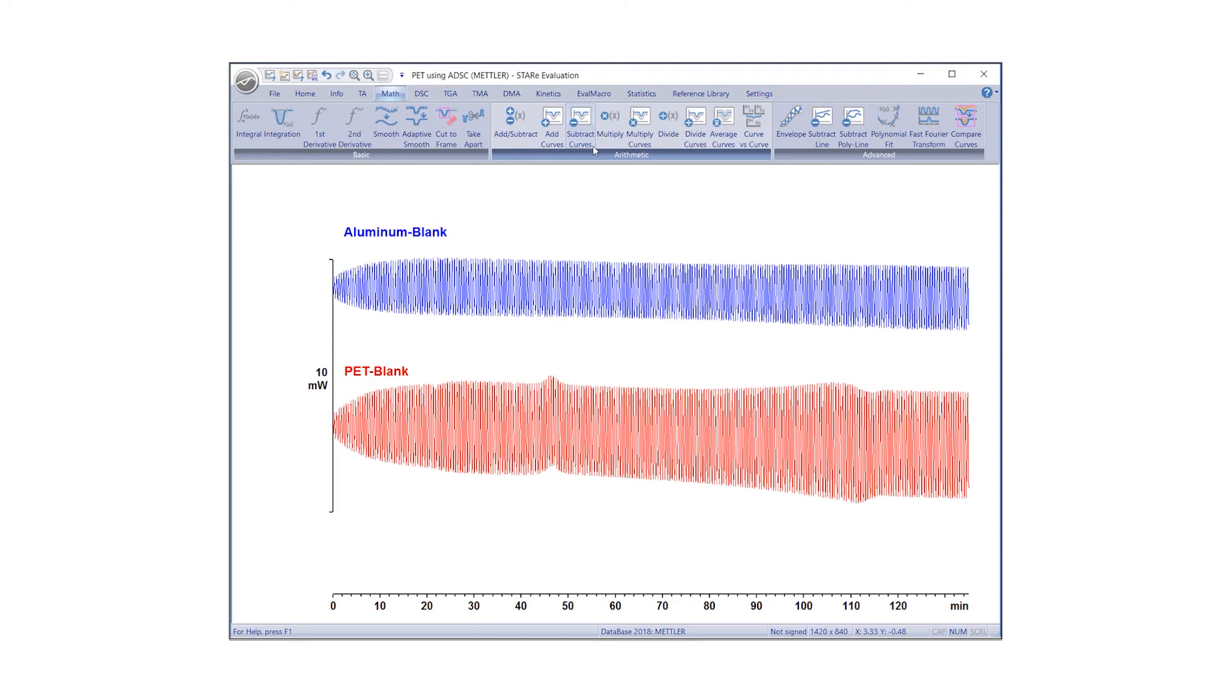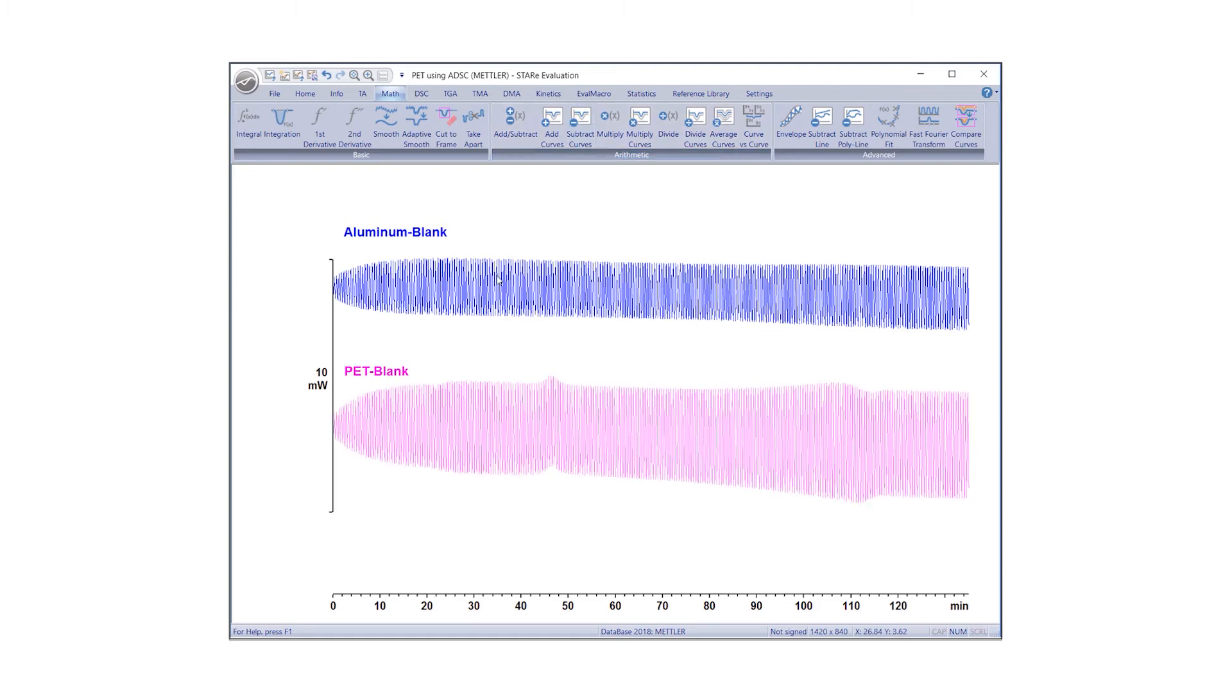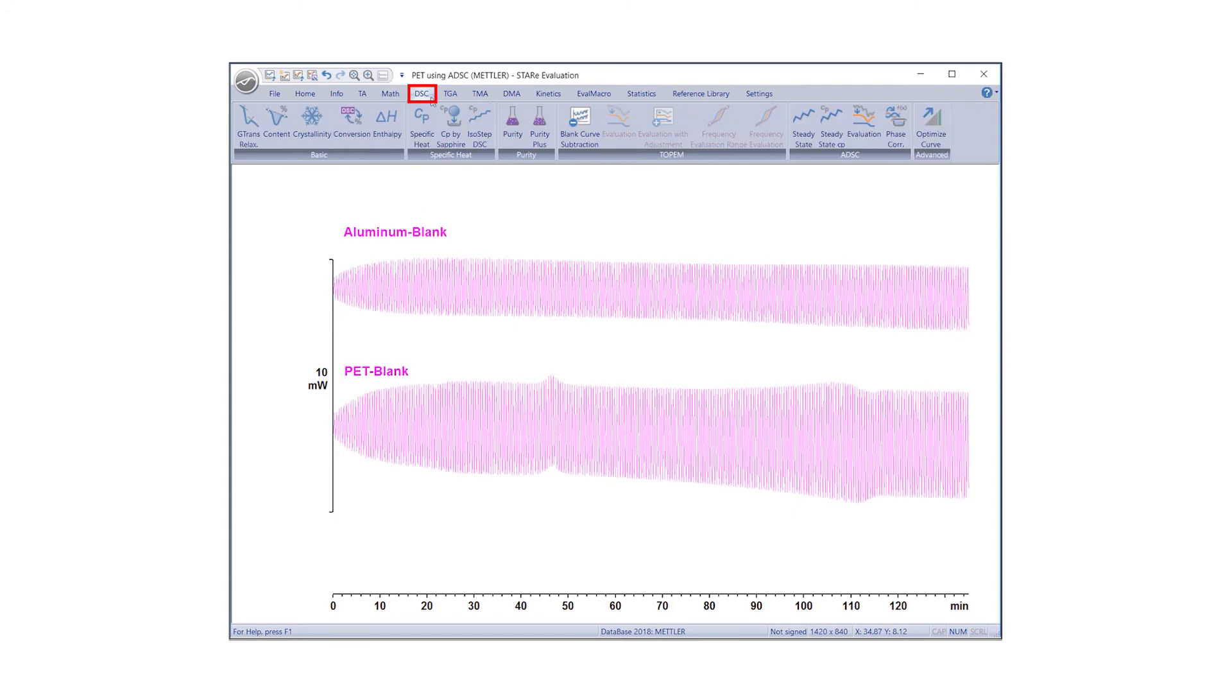Step 3, calculate the heat capacity, phase angle and reversing, non-reversing, and total heat flow curves. First, select both blank corrected curves. Then, under the DSC tab, select Evaluation for ADSC. Set the Calculation Depth and Reduction Factor to 1. The Reduction Factor is the reducing number of measuring points for the ADSC evaluation. A period of 60 seconds is chosen based on the method's loop period.